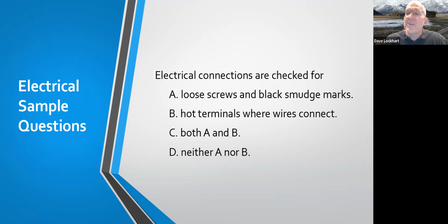All right, electrical connections are checked for A, loose screws and black smudge marks, B, hot terminals where wires connect, C, A and B, or D, neither A nor B. And that is correct, both A and B. Hot terminals where wires connect. That's usually done with a thermometer or thermography imaging scanner to check for hot stuff. You may be able to check the wires when the power is off to see if they feel hot, but oftentimes it's loose. You can see a loose screw, wires are loose, or black smudge from the arcing and the heat that is created from loose connections. So great answer there.